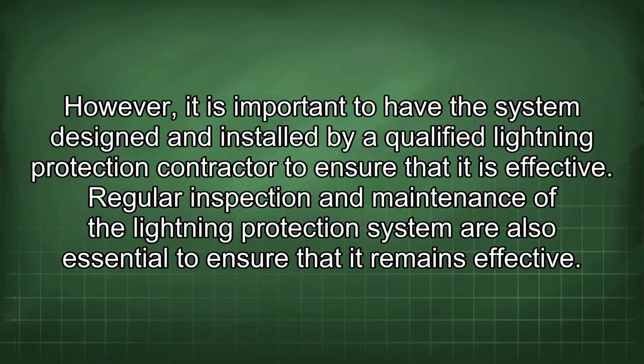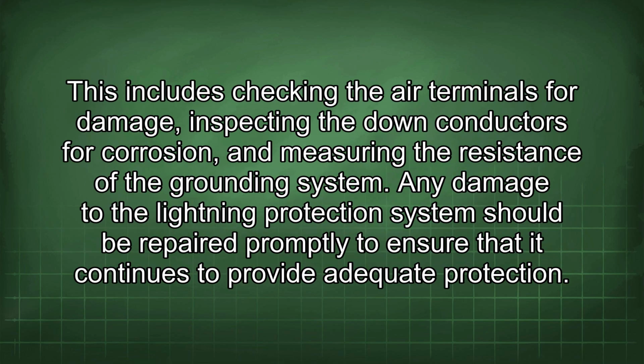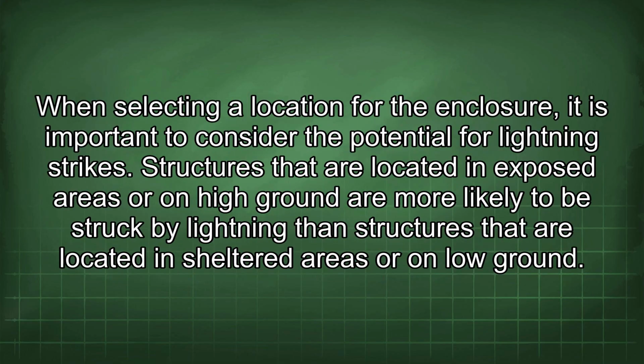Regular inspection and maintenance of the lightning protection system are also essential to ensure that it remains effective. This includes checking the air terminals for damage, inspecting the down conductors for corrosion, and measuring the resistance of the grounding system. Any damage to the lightning protection system should be repaired promptly to ensure that it continues to provide adequate protection. When selecting a location for the enclosure, it is important to consider the potential for lightning strikes.